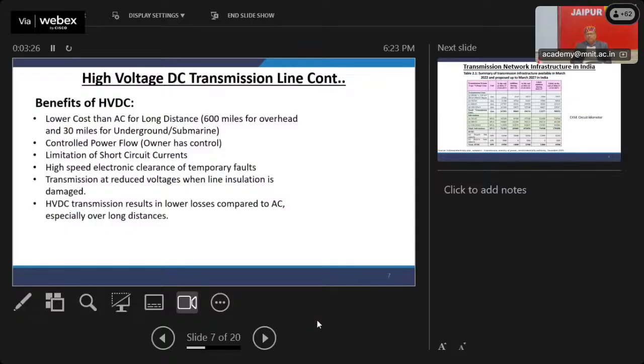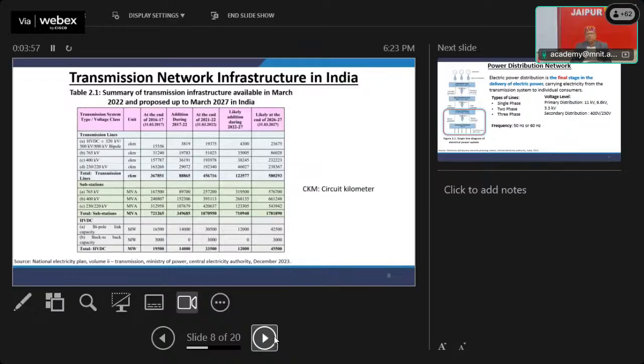So, what are the benefits? Lower cost than AC for long distance, that is beyond 600 miles, and 30 miles for underground and submarine. Controlled power flow, the owner has control. Limitation of short circuit current. High speed electronic clearance of temporary faults. Transmission at reduced voltage when line insulation is damaged. HVDC transmission results in lower losses compared to AC, especially over long distances.